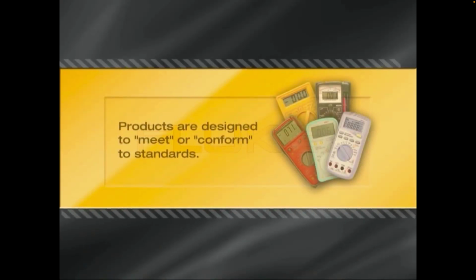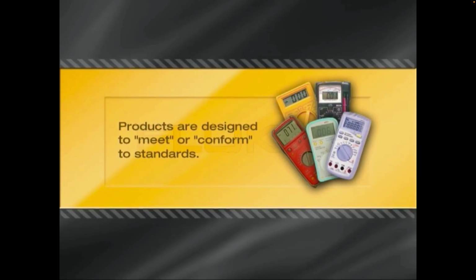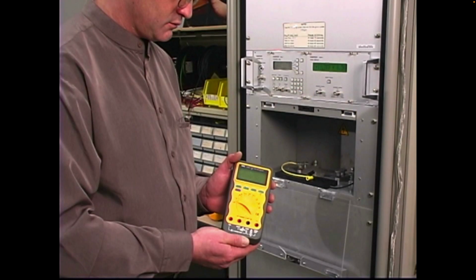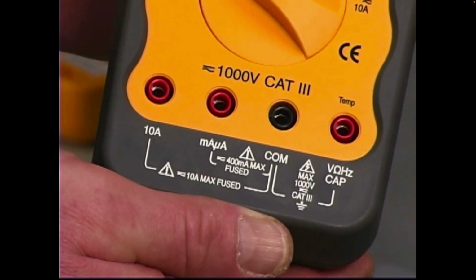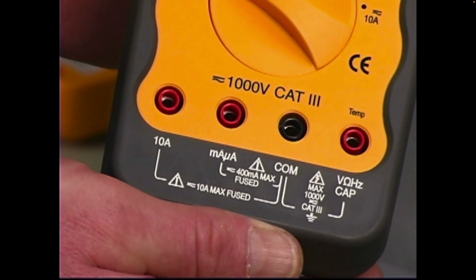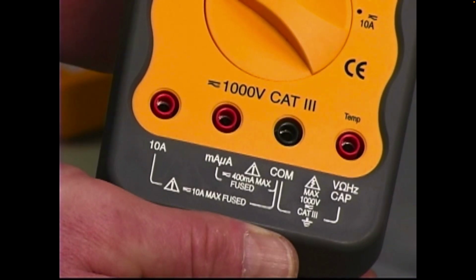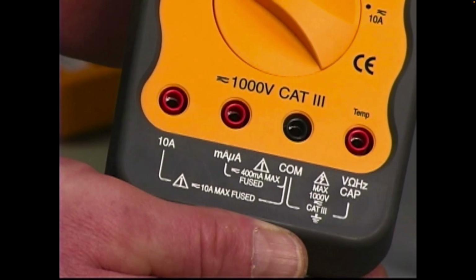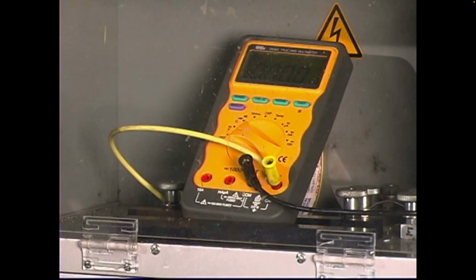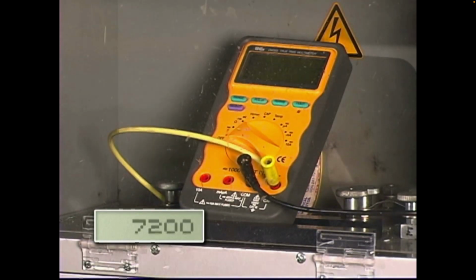Some manufacturers state that their products are designed to meet or conform to standards, but not every meter or tester that makes that claim will pass the test. Here's what happened when one meter, marked 1000 volts Cat 3, was actually tested. The meter is supposed to withstand a minimum of 20 transients of 8 kilovolts each, but this meter failed twice before reaching the 8 kilovolt minimum level.